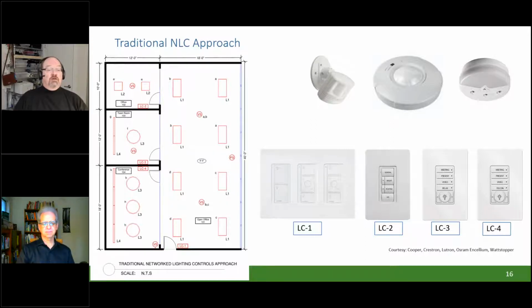Outstanding question. For most manufacturers, the difference between an occupancy sensor and a vacancy sensor is one of either programming or dip switch setting. With an occupancy sensor, you walk into the space and lights come on; you leave the space and eventually lights go off. With a vacancy sensor, you walk into the space and nothing happens—you have to push a button, then the lights go on. Once you leave, they'll automatically go off. I like that, because if you're just dropping a folder off on your boss's desk, you don't need the lights on for 20 minutes.